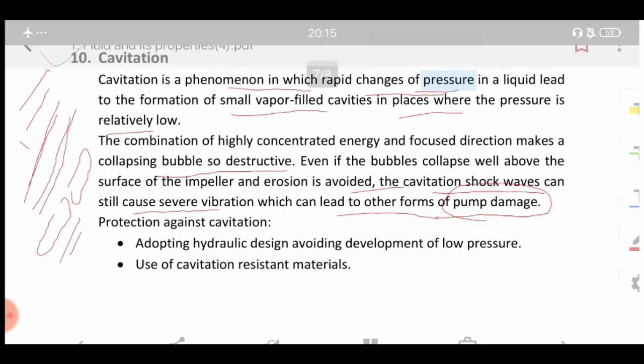Even if the bubbles collapse well above the surface of the impeller and erosion is avoided, the cavitation shock waves can still cause severe vibration, which can lead to other forms of pump damage. It can be seen in pumps or even in certain pipes. Whenever you are lifting water with a pump or a tube well and touch the pipe or conduit through which the water is being lifted, you will feel a little bit of vibratory force, as if the fluid flowing is not continuous. This is generally because of cavitation, and it is very harmful for the pipes, conduits, or even the pumps.